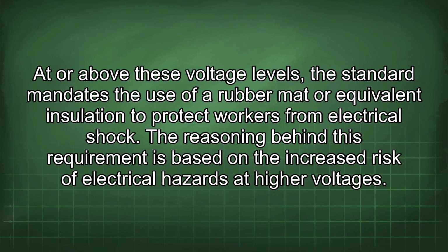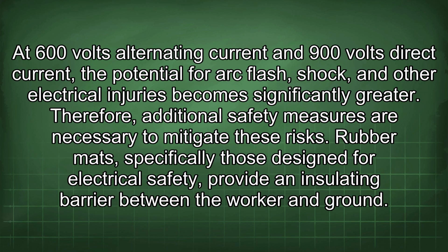At or above these voltage levels, the standard mandates the use of a rubber mat or equivalent insulation to protect workers from electrical shock. The reasoning behind this requirement is based on the increased risk of electrical hazards at higher voltages. At 600 volts alternating current and 900 volts direct current, the potential for arc flash, shock, and other electrical injuries becomes significantly greater. Therefore, additional safety measures are necessary to mitigate these risks.